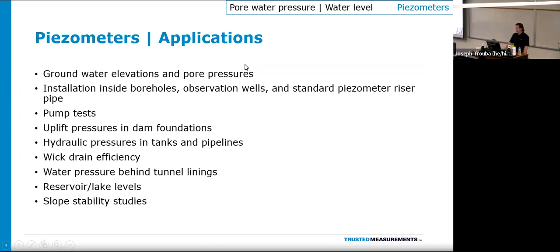So piezometers, some applications for piezometers. They basically obtain groundwater elevation and pore pressure measurements. They're often installed inside boreholes, observation wells, and standard piezometer riser pipe. They can be used during pump tests, measuring uplift pressures in dam foundations, hydraulic pressures in tanks and pipelines, wick drain efficiency measurements, water pressure behind tunnel linings for underground applications, reservoir and lake levels, as well as weir levels, and slope stability studies.